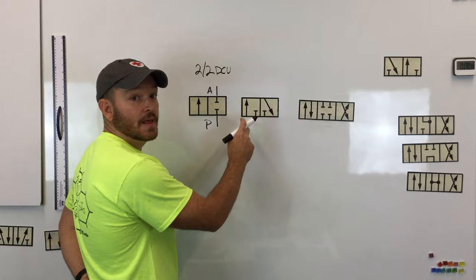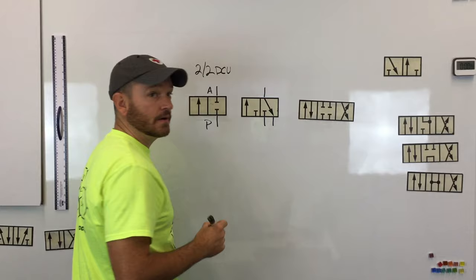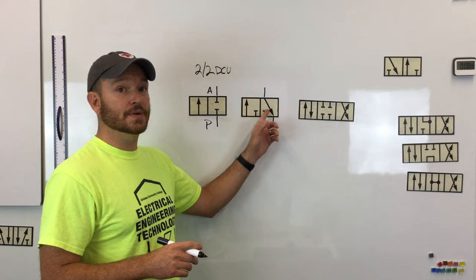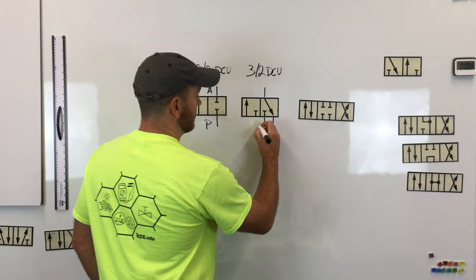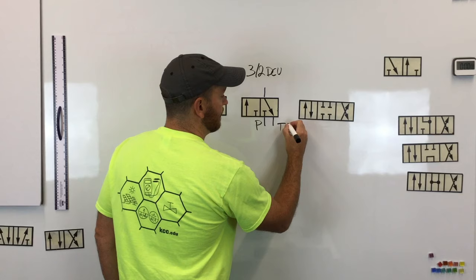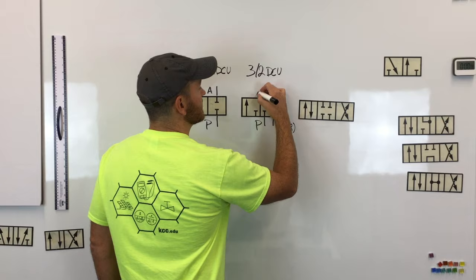This next valve has two positions but three ways associated with it, meaning it has one port here, one port here, and one port here. This would be a three-way, two-position directional control valve, or a three-two directional control valve. The P is on the bottom left, the tank port — sometimes referred to as the reservoir — is on the bottom right, and the top port is always identified as the A port.